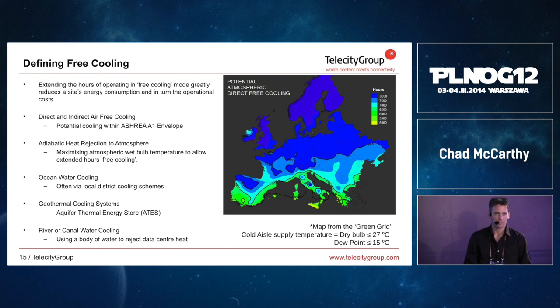That can be problematic if there is smoke, smog, a certain degree of pollution, or a fire anywhere nearby. That leads people to what we call indirect free cooling, where you exchange the air over a heat exchanger. So you lose a couple of degrees, and this changes the diagram. If you have indirect free cooling, then the colors in the diagram kind of move to the top.